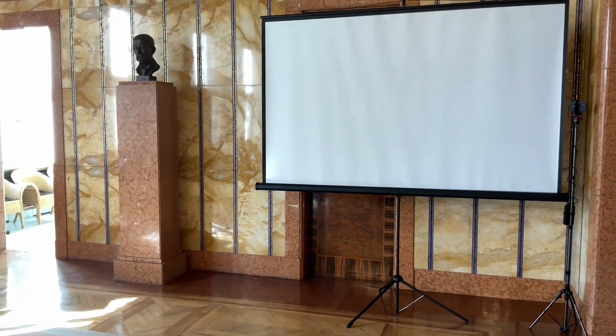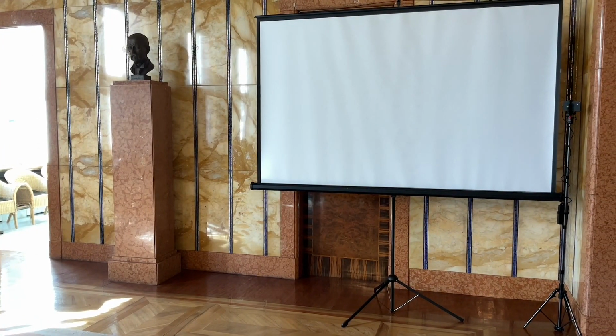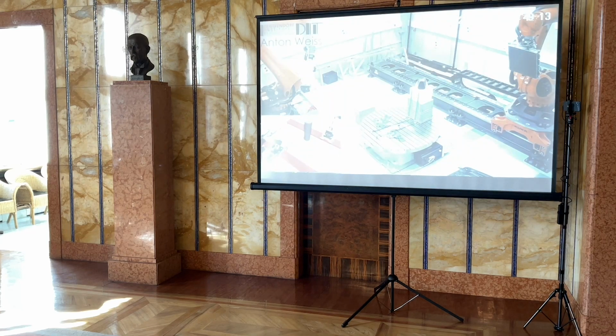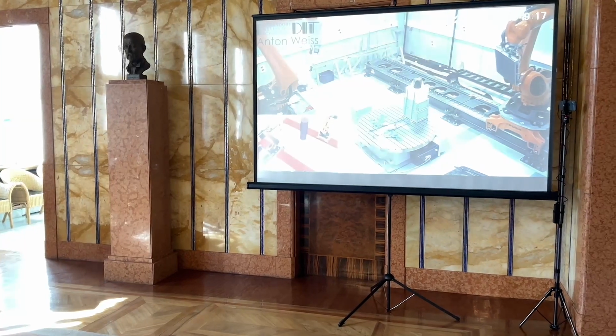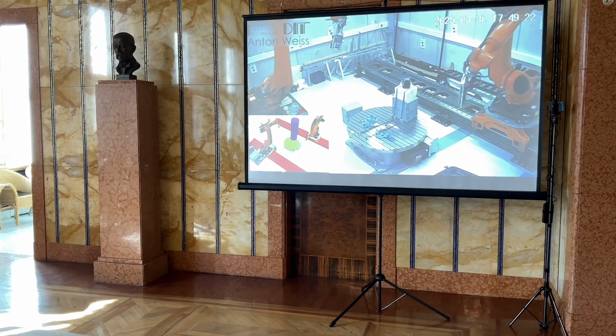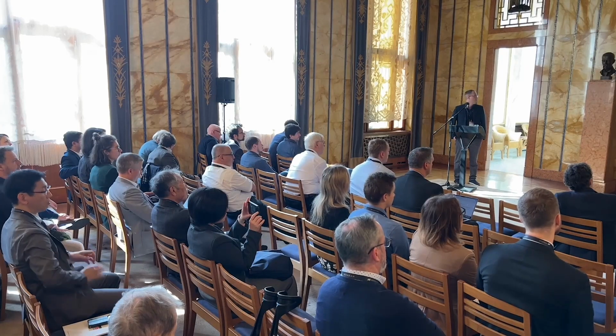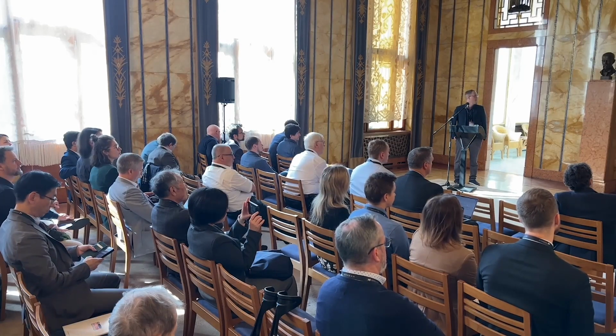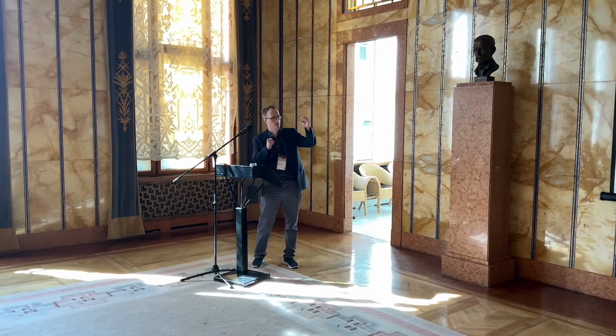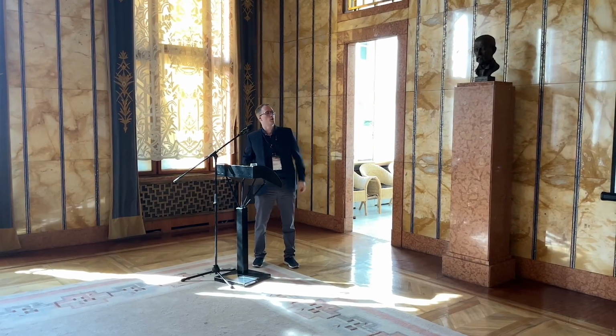Okay, so let's start with speed. One of the things we're doing right now is flyby scans. What does it mean? It means that the RoboCT doesn't have to stop when it takes a picture. So it does a continuous movement. And this continuous movement, it takes pictures, and when it starts, it just continuously makes images. What it does here is something like a sinusoidal trajectory around this test object.